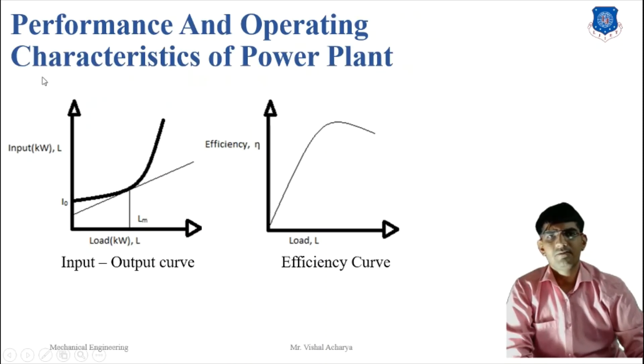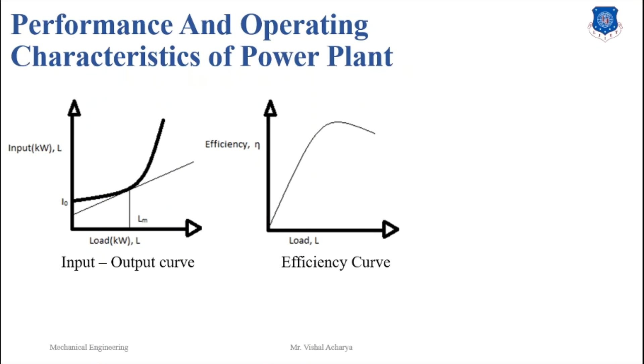Next is the performance and operating characteristics of power plants. The performance of a generating power plant is compared by the average efficiency over a period of time. Average efficiency is the ratio of useful energy output to total energy input during the period considered. The performance of the plant can be precisely represented by the input-output curve from tests conducted on the individual power plant. The input is generally expressed in megajoules per hour and load output in megawatts. For hydro power plants, the input is measured in cubic meters per second of water.